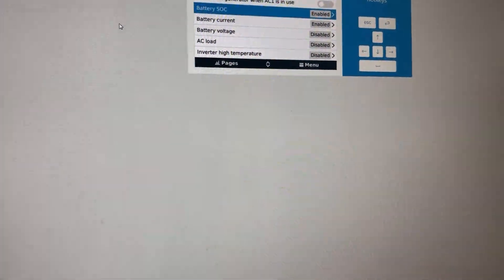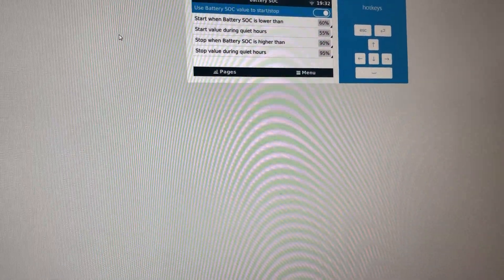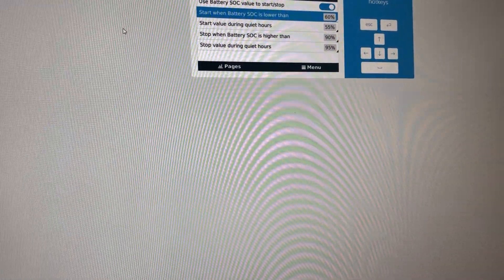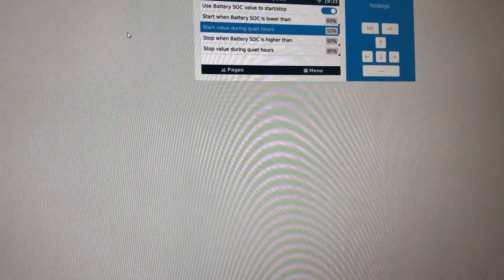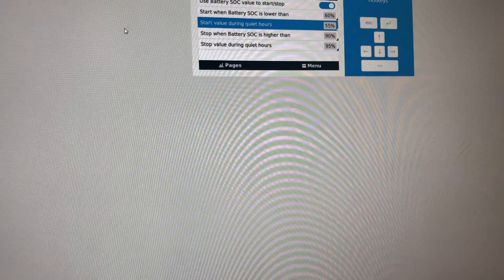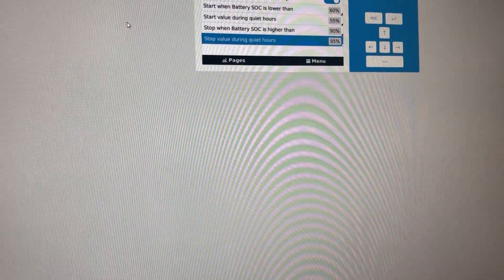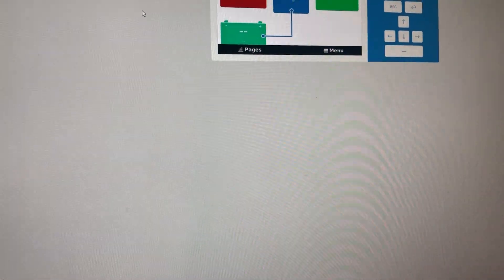I can go by battery state of charge, which is depth of discharge. I need to run my generator when my battery's down to 60% and stop my generator once we're running at 90%. During quiet hours at night, I may not want to start my generator unless absolutely necessary at 55%. And since there's no solar, I might want to charge my battery bank up to 95%. The configuration of this is really cool.